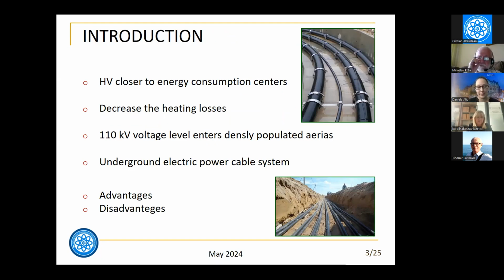Hence, in order to decrease operational joule losses, the three-phase high-voltage electrical system is frequently positioned in the middle of the consumer's area, applying a buried three-phase cable system. The position of the single high-voltage cables in constructed concrete corridors or directly buried in soil can be in triangle, in trefoil, or in line, and both systems were analyzed together with their electric and magnetic fields.